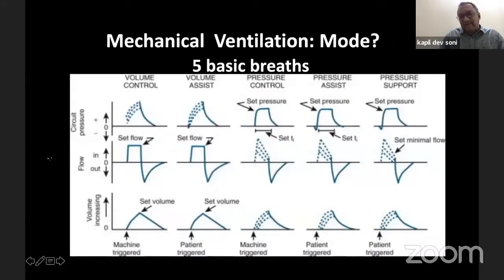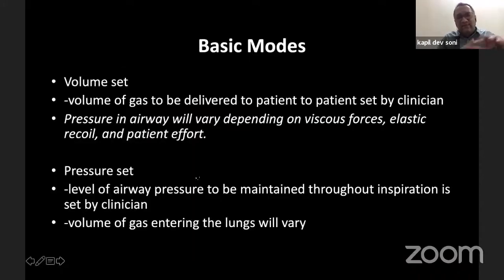So ideally, there are 5 basic breaths. Based on different modes, a patient can have a control mode, an assist mode, or a support mode. Just a play of variables: one is pressure, flow, volume, time. These are 4 variables, and based on the combinations of all these 4 variables, different breaths are designed. A basic mode is the volume set or pressure set. A volume set or volume control breath means a specific volume of gas would be delivered to the patient, and that's been fixed. On the other hand, the pressure, flow, and time may vary.